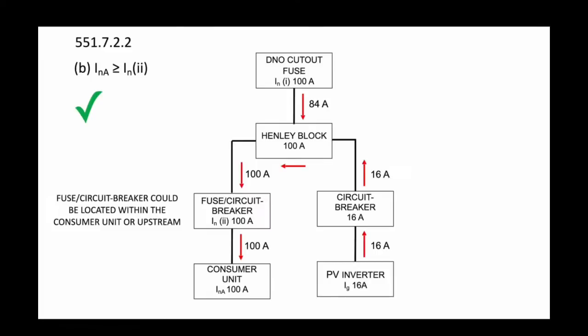But by doing that, we've now held the rating of the consumer unit at the rated value of the second one up, circuit breaker or fuse. So we've got overload coordination again. That's what we're looking for, ignoring fusing factors. We shouldn't be relying on a fuse to provide overcurrent protection. That should be the designer's responsibility, to ensure that it can't go over that.